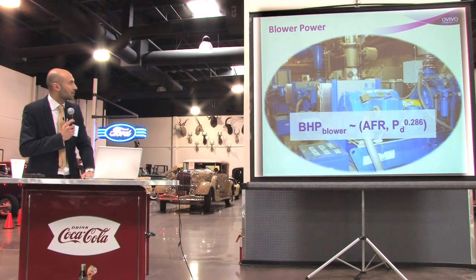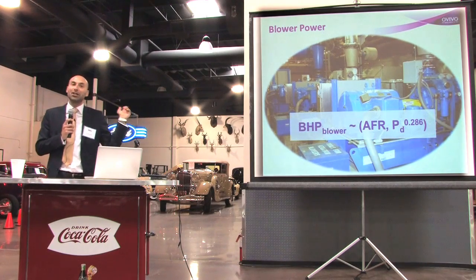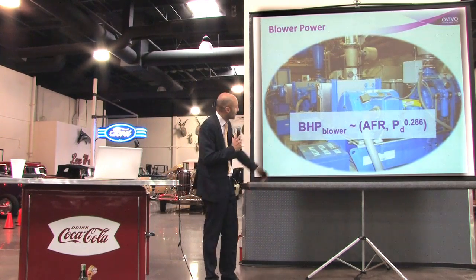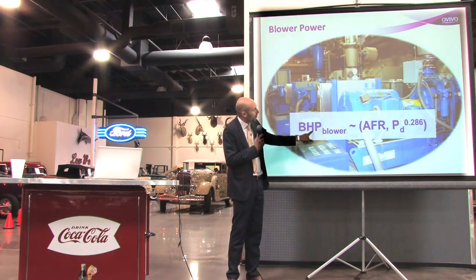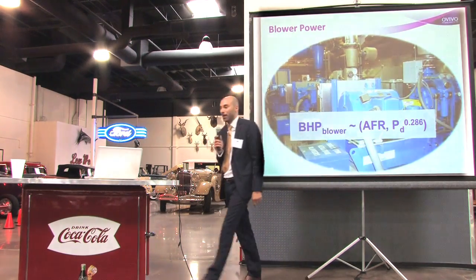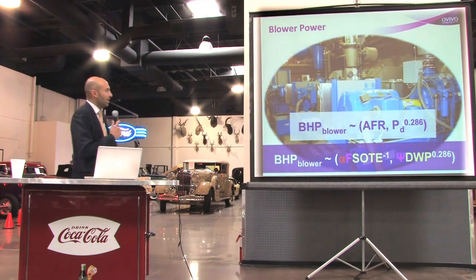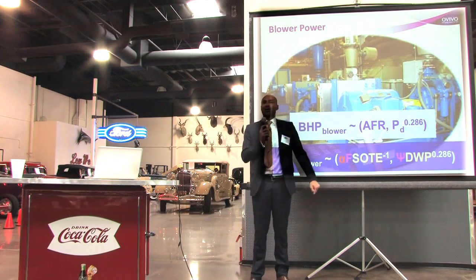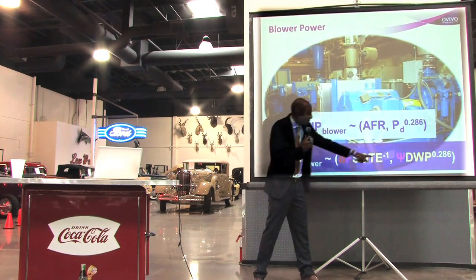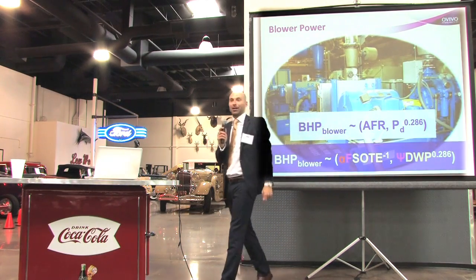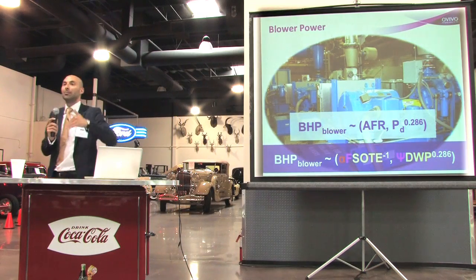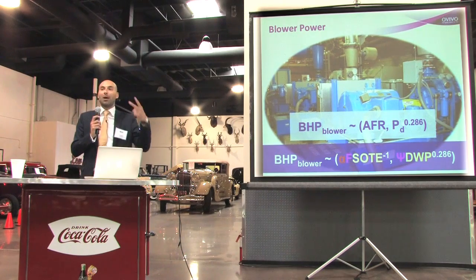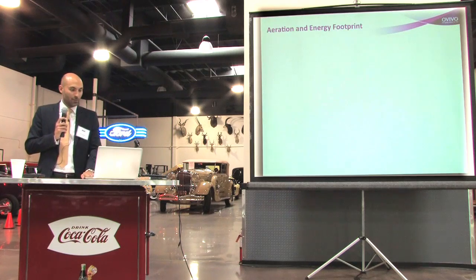The blower power formula (Metcalf & Eddy, Equation 5-56a) shows blower power is proportional to airflow rate and discharge pressure. Over time, airflow rate is inversely proportional to alpha·SOTE (which declines), and pressure increases — so two factors compound against you simultaneously, driving the power bill higher.